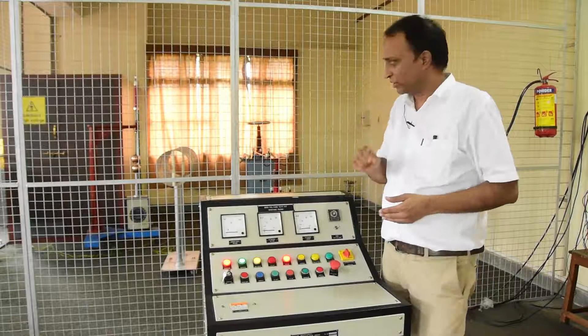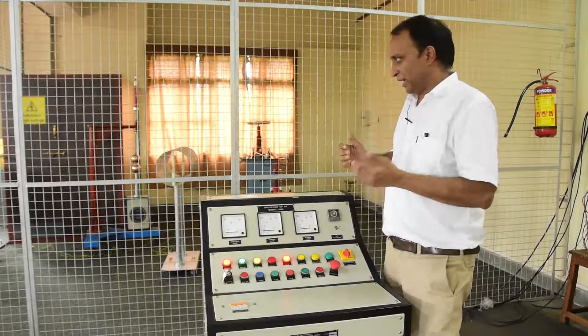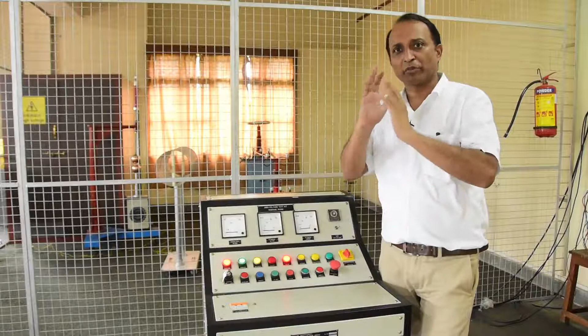It's a very small hissing noise, because these conductors are not actually power conductors. In this lab test condition, we are just giving the high voltage and observing the corona phenomena. The dimensions and everything are standard, but it is not a power conductor supplying power to the actual load. That's why a very dense hissing noise will not be heard. So we want to find the inception voltage. Inception is just the beginning, so a very thin, very small noise will be there. So silence must be maintained in order to note down the presence of audible corona.